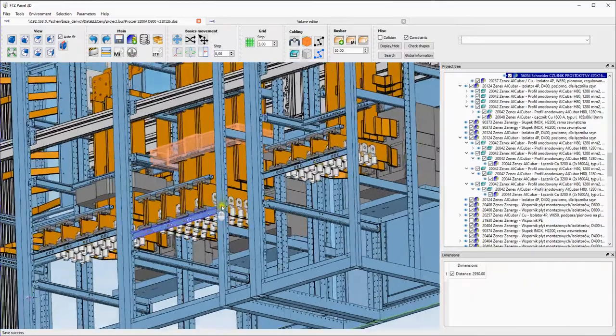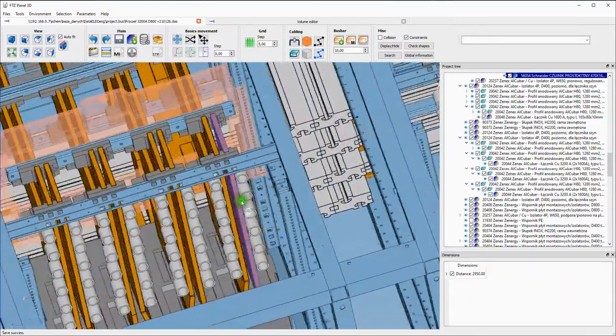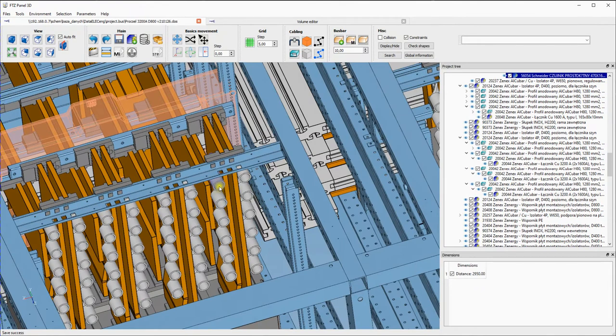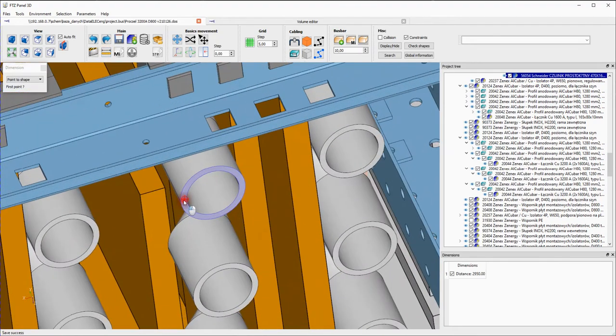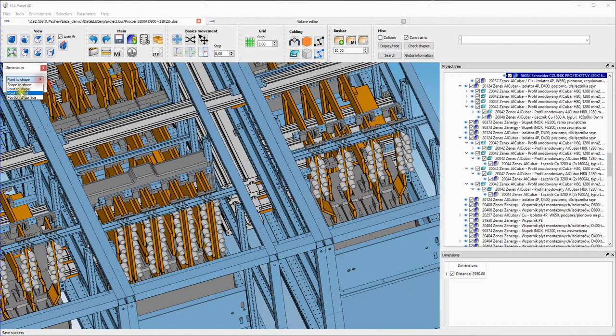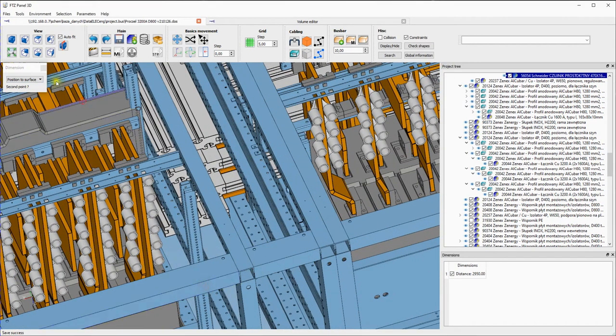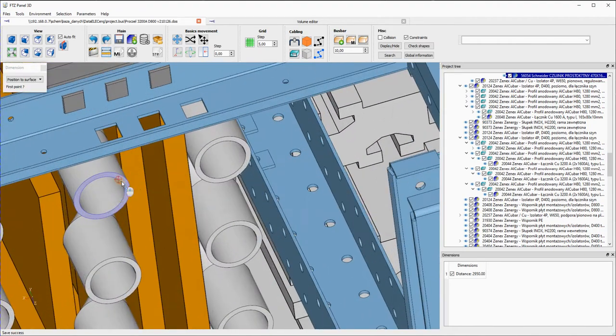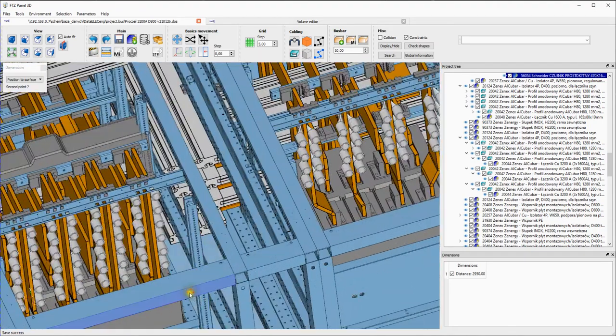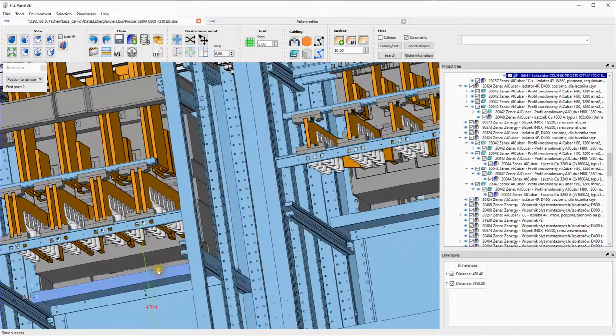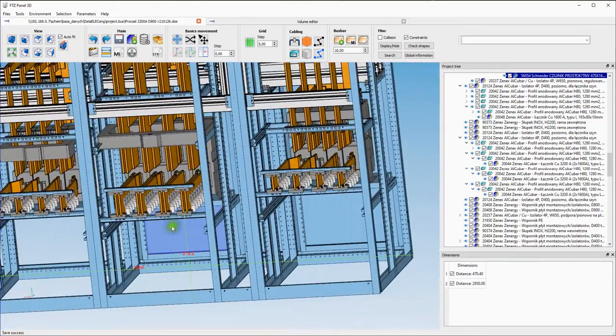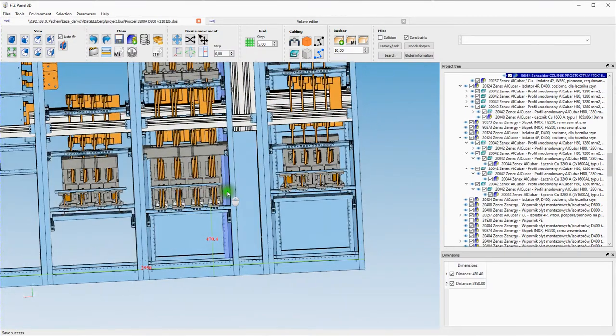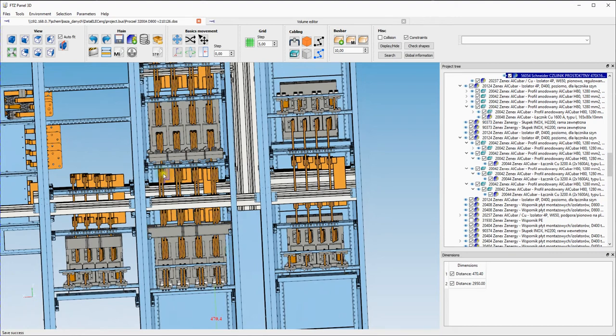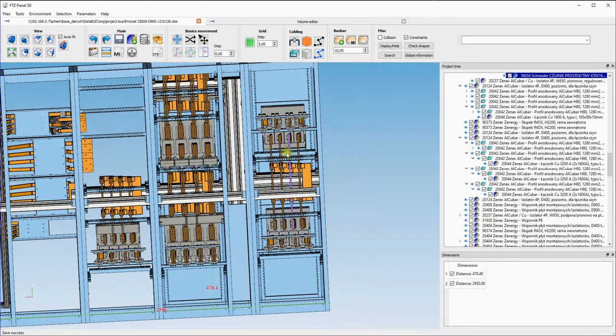Yeah, it is already quite low, and here you have this 3200, 2500, so 1, 2, 3, 4, 5, 6, 12 cables. And if we measure the distance from here to the surface, again from here to the surface, we have 470 millimeters. So I hope it's enough for the cables. Because of this big breaker and those bus bars, it is a little bit lower than those smaller breakers.